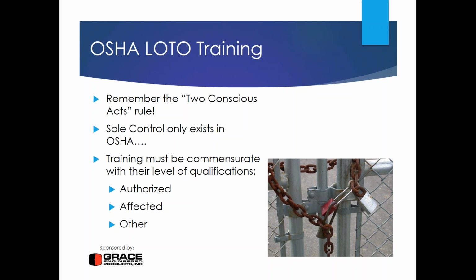So if you don't know what else to do on a circuit and it's not lockable by design, go with the Two Conscious Act rule and you'll get compliance by default. The idea of sole control only exists in the OSHA standard itself. It doesn't exist really in the 70E anymore. And sole control simply means that if you have sole control over the energy isolating device, known as an EID, that means you do not need to lock out, tag out that device.